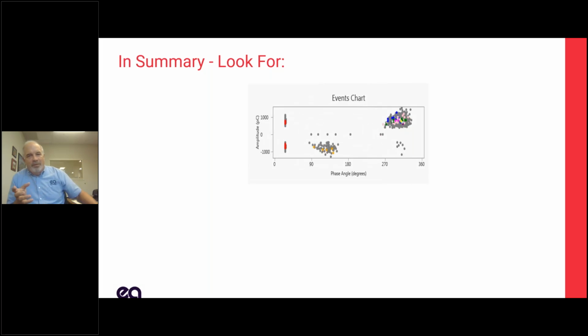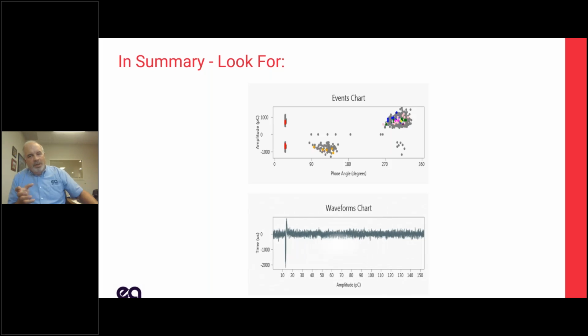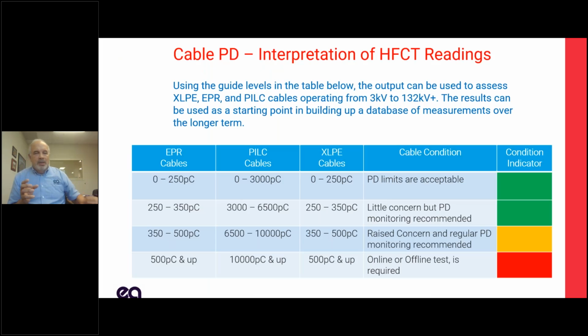So in summary, we're going to look for our events. We're going to look at our waveforms, look for 2 clusters 180 degrees apart, and we're going to look for a spike that is indicative of PD. The levels are tough. With an offline test, you can have exact levels and you can see what the PD is. We look at levels, but we're more worried about the pattern, and we're more worried about how clean the waveforms are. We're not going to get too excited about the levels. If they are very low, it's not a concern. If they're very high, it's a concern, but the borderline stuff, just keep testing, seeing if it gets worse.